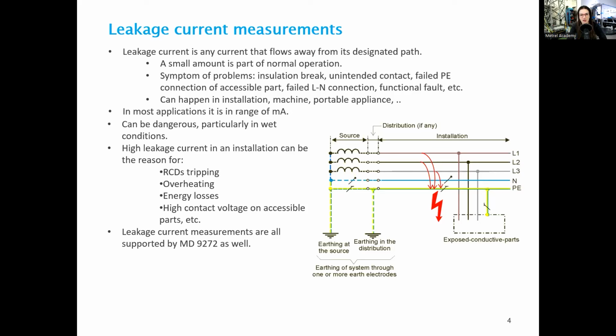The normal level, the everyday level of leakage current, is very rarely dangerous. Perhaps the only occurrence where this can happen is if an installation that was not designed for moist or wet environments suddenly gets wet. However, if leakage current becomes different from this basic expected level, then it can be taken as a symptom of problems. It can be a symptom of installation break, unintended contact, a failed connection of an accessible part, a failed connection between line and neutral, functional fault, and similar problems. The source of this fault can be anywhere. It can be in the installation, in a machine, or in a portable appliance.